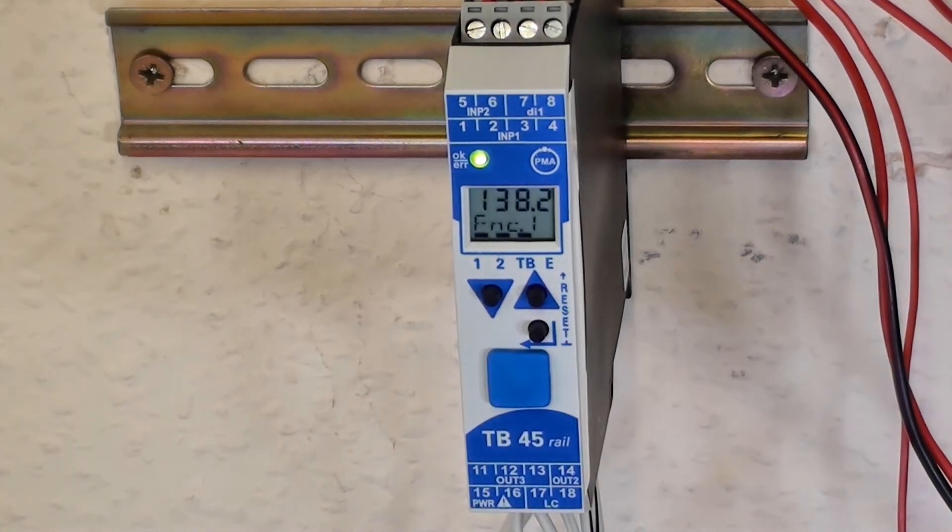Limit. The function for that limit alarm, the LC alarm, I've selected function 7. And from the lookup table, F7 means I've selected it as a temperature limiter.